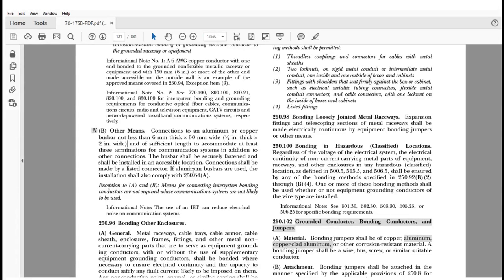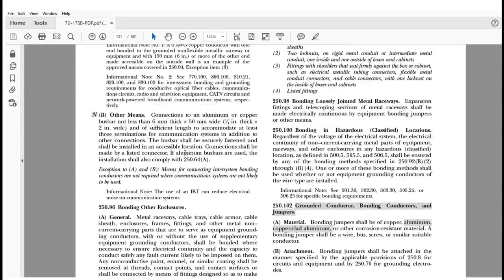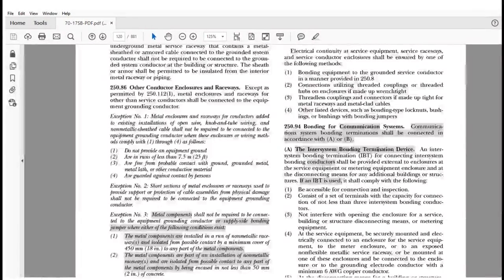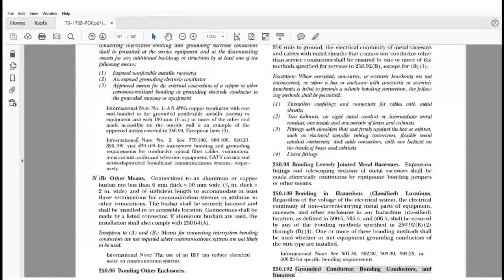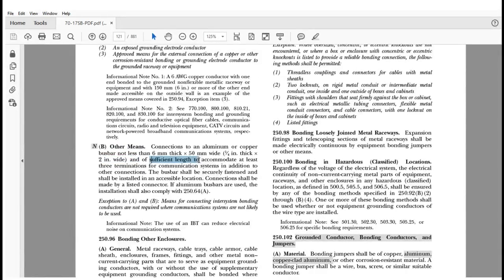All right? So that was the significant change. We gave you a bone here. You can do this. But that doesn't mean that you can go out and buy one of those listed inter-system bonding devices that is designed for communication, that's listed for communication, as expressed in the code. Again, as it's stated here, if you want to bring other things to that location, then you're going to have to use the other means application and make sure it's the right size bus bar, make sure you install it right, and make sure it has sufficient length to accommodate all the potential terminals that you want, and at least 3 for communications.